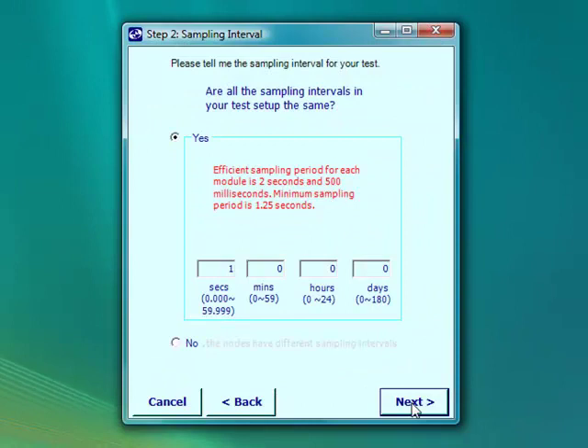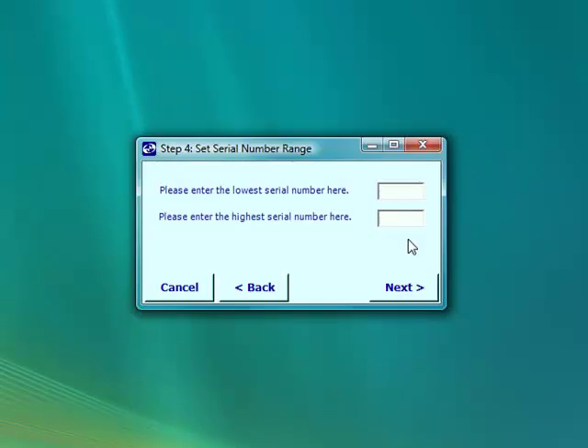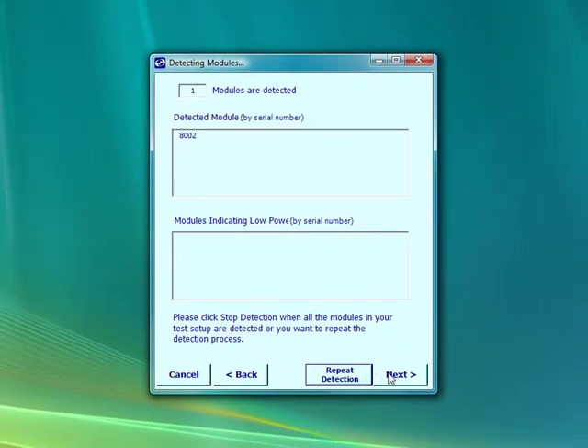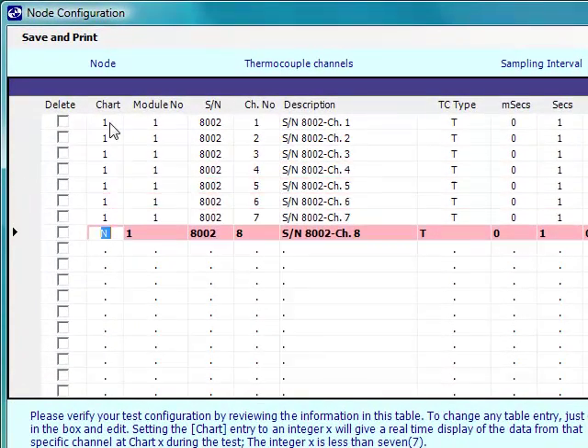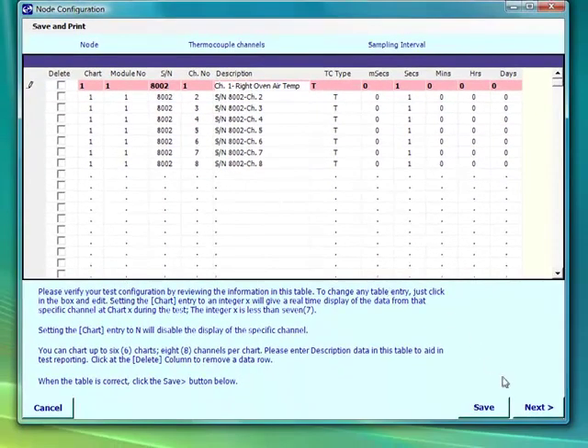Entering 10 for the number of modules gives us extra time for detecting modules. Sampling rate is fine. Here we need to select T-type thermocouples. We're using module 8,002, so the lowest serial number is 8,000 and we enter 9,000 for the highest serial number. We see that 8,002 is detected, so we click Stop Detection and move on. In the configuration chart, we need to change the chart to number 1 so that all 8 channels appear in chart number 1. Now we can use the description column to label each channel with a descriptive name, such as Right, Oven, Air, Temperature. We're ready to save the file.